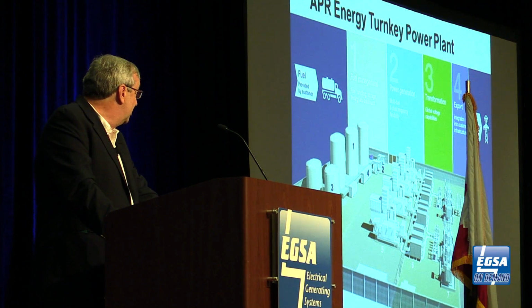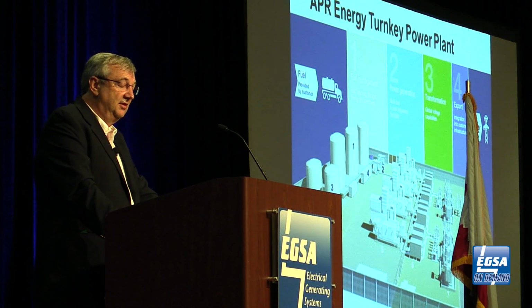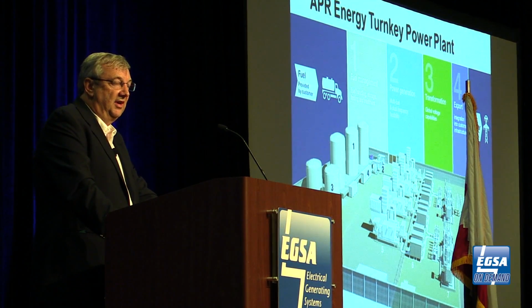And doing it in a 20-foot footprint gives flexibility and ease of movement. We don't have the challenges of roads and bridges not being able to take the weight of bringing in a 70 MVA power transformer. You're coming in with 35 tons of transformer dry, with all the accessories taken off. That's workable, it's doable, infrastructure in these countries can handle that. You come in with a 150 ton transformer, that creates a lot of challenges. You need the trailers to put it on, you need to find the cranes to move it. It just becomes a logistics challenge.